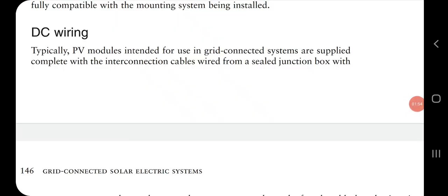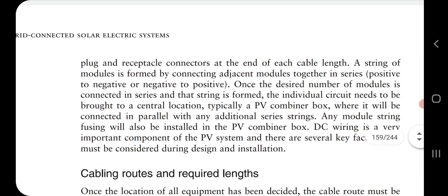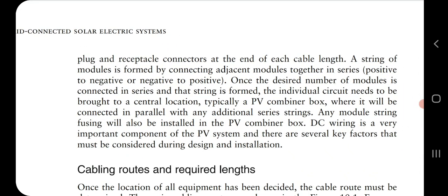Now see, in the DC wiring, the PV modules have to be connected properly, the connections have to be given, and the wires have to be used. A sealed junction box has to be used, and the plugs and receptacle connectors are provided at both ends of the wiring. A number of modules should be connected in a string, positive to negative and negative to positive, creating a big string. That string has to be brought to a particular area and connected to the PV combiner box.